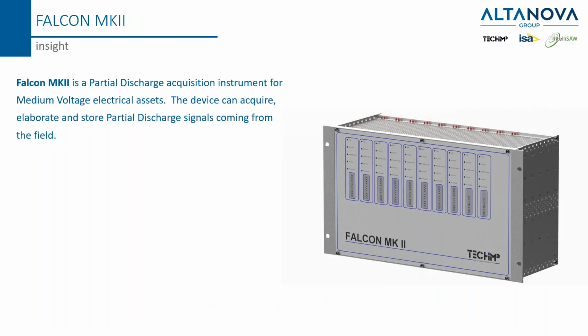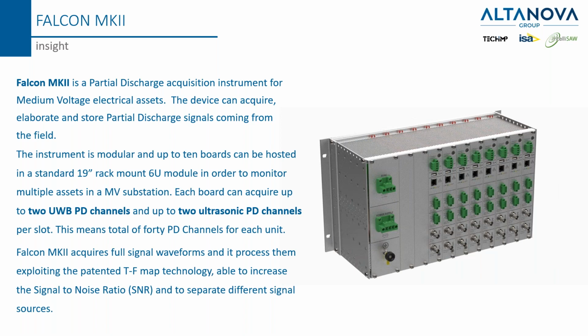Some insight. The Falcon Mark II is an evolution of the partial discharge acquisition instruments for medium voltage assets. It comes in a 19 inch rack, and it is a modular system that can host up to 10 boards, mounted in a 6-unit high rack. Each board can acquire up to 2 ultra-wide bandwidth channels, for example for partial discharge, typically by means of the HFCT or the TEV, plus 2 ultrasonic PD channels per slot. That means in total up to 40 partial discharge channels for each unit.